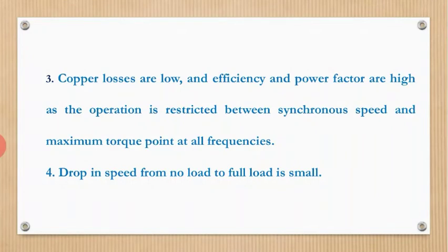Next, the copper losses are low and efficiency and power factor are high, as the operation is restricted between the synchronous speed and maximum torque point at all frequencies. Then the last one: the drop in speed from no load to full load is small. It means that even when you are fully loaded, the drop is less.